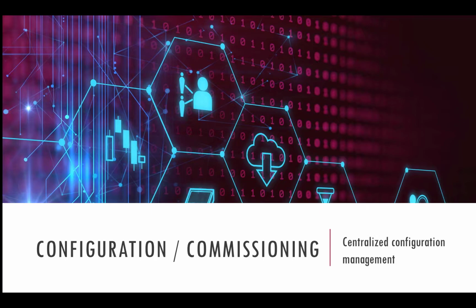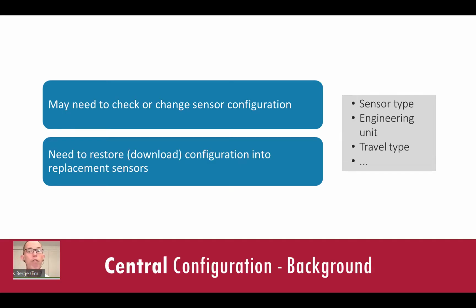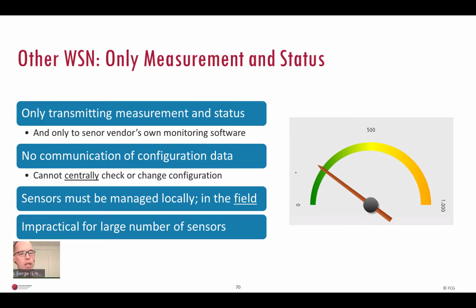Now, configuration management. You may need to check or change the configuration of sensors, such as changing sensor type, engineering unit, and travel type, etc. You may need to restore configuration into a replacement sensor. But some wireless sensor network technologies only transmit measurement and status. There is no communication of configuration data to or from the sensor. That is, you cannot centrally check or change sensor configuration. You must go to the field to check or change sensor configuration locally at the sensor. This is impractical, particularly for large number of sensors or offshore.